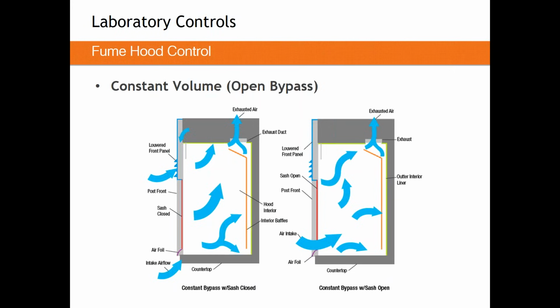Constant volume fume hoods should be used when they don't inflate your makeup air number. So for example, if you have a thermally driven or a ventilation driven laboratory, you should probably use a constant volume fume hood. For example, if we need 1,000 CFM of supply and 1,100 CFM of exhaust to make the room negative, and my fume hood at maximum only consumes 500 CFM, that's a great way to use a constant volume fume hood. Opening and closing that sash will save you nothing for energy because we already needed to make that air up for ventilation or thermal demand.